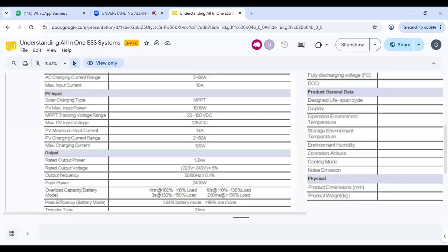Which means if your solar panel is just about maybe 30 volts or 40, it will work and deliver the required power. Then look at the maximum PV input to the MPPT, which is 125, which I don't advise anybody to operate, because that's the maximum. If you are operating at that range, then if anything happens and your voltage spikes up, you can get it damaged if it goes beyond it. It is stated clearly that's the maximum you can take.